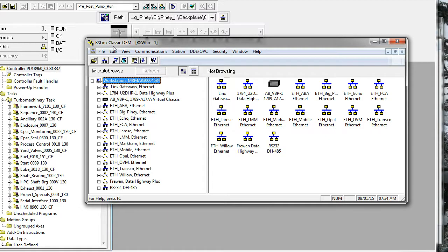This often causes problems when updating a logic package. People make the mistake of also installing the RSLinx that comes with it and overriding their Classic OEM or whatever other version they had previously installed — and they lose their OPC server. The software package for RSLinx is actually one version; what features are enabled depend on what's been activated in the activation manager. So if you've lost your OPC server when you've updated ControlLogix or RSLogix 5, what you need to do is reset your activation for RSLinx. You don't need to do a full reinstall.